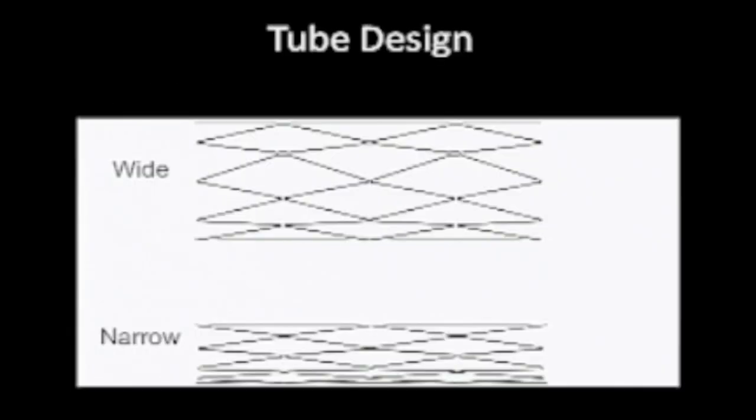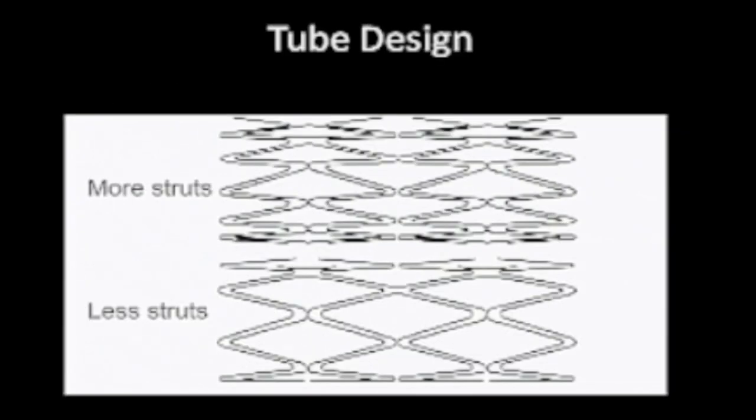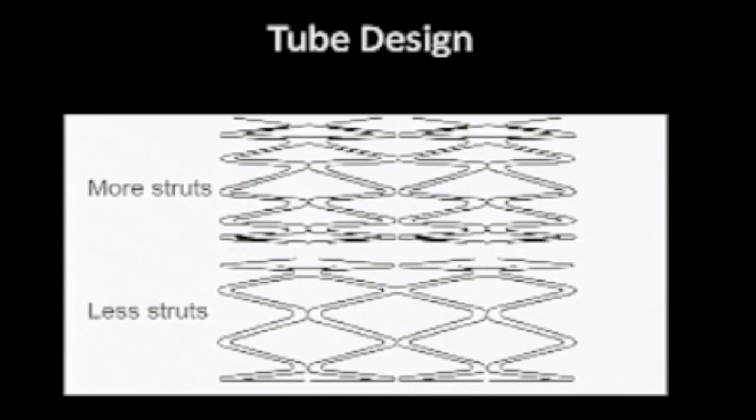Tube designs can be wide versus narrow with more or fewer struts. Thin struts range from 50 to 75 micrometers versus thick struts which go up to 140 micrometers. Literature reports that thin struts are associated with a reduction of restenosis in arterial applications, though there is very little data to support this in veins.